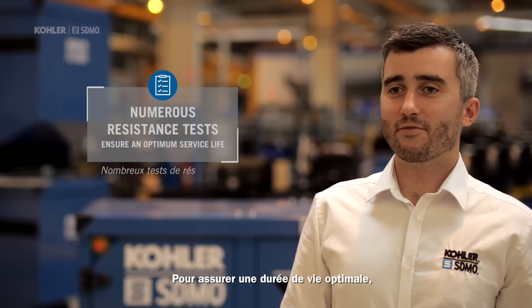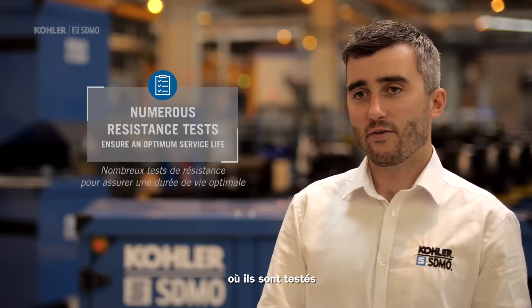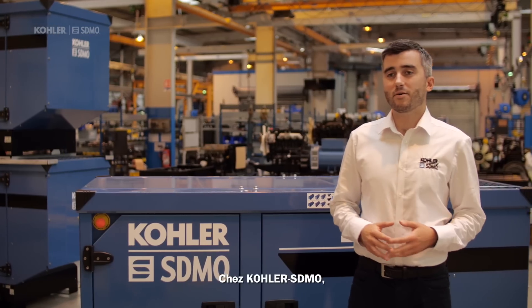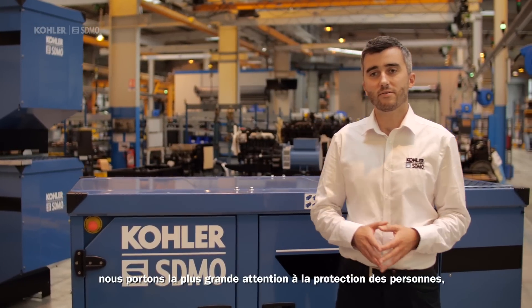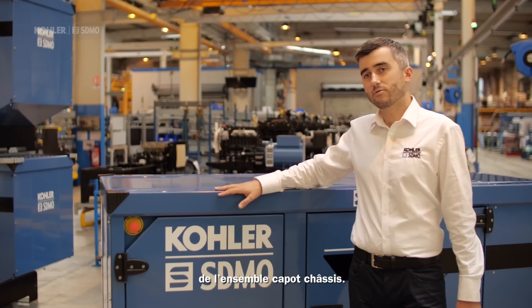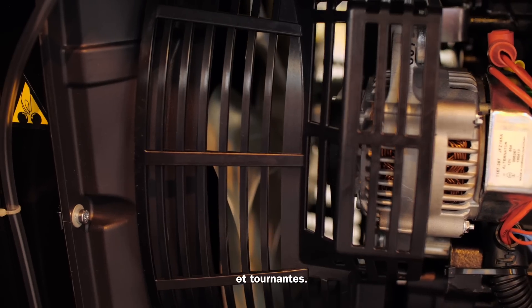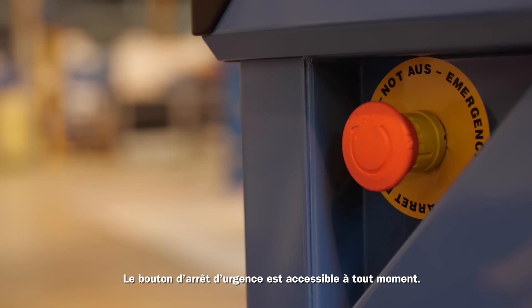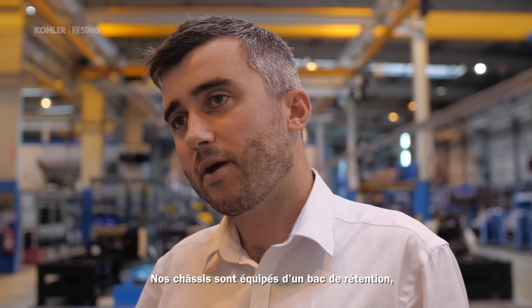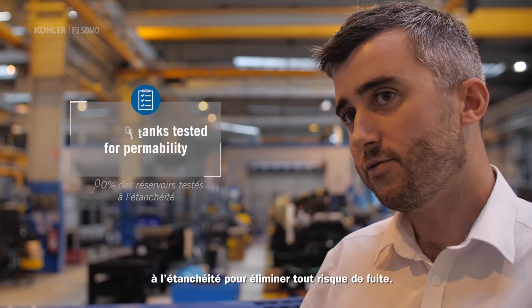To ensure an optimum service life, our base frames and enclosures are sent to the French Institute of Corrosion, where they are tested and exposed to salt spray for more than 1000 hours. At Kohler-SDMO, we pay the greatest attention to the protection of persons, installation and environment. We ensure the electrical continuity between the base frame and the enclosure. Our operators are protected against hot and rotating parts. We give full access at any time to the emergency stop button. We use IP64 stainless locks. Our base frame comes with a retention band, and 100% of our fuel tanks are tested for permeability to avoid any fuel leaks.